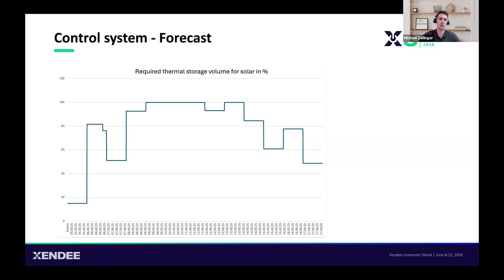It can also only use 20% of the storage volume, and the other volume needs to be unused by the biomass boiler and kept free for the solar system. The objective here is not a perfect prediction, but even with moderate forecast accuracy, it can make a significant difference when it comes to improving solar integration and avoiding unnecessary boiler operation.